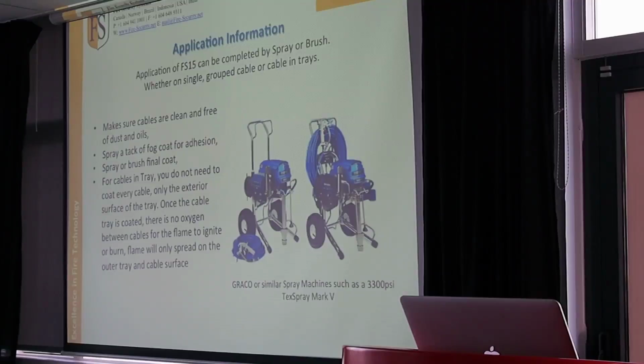And for us, in applying the product, we have to make sure the cables are clean and free of dust and oils. If there's a heavy amount of oil on it, we'll use a watered down solvent to get that oil off, because we simply need to stick to the electrical cable. So we spray a very light coating onto the cable for adhesion, and then we spray or brush a final coat. Majority of the time we spray the coating because the finish is always better, plus it's a lower amount of contract time. Brushing the coating, although it's still going to do the same thing, is a very ugly application. It just does not look good in the end run.